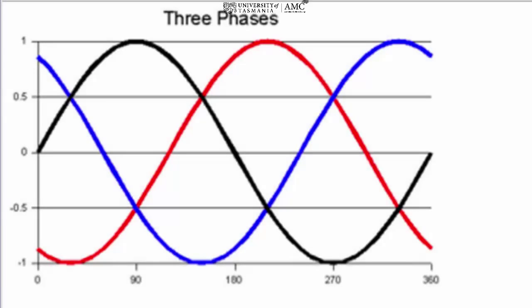The process of paralleling or synchronizing two generators or two alternators is essentially this: we have one generator which is on the board and it's producing our three-phase AC 415 volts, and you can see the three phases here as blue, black and red. Now if we want another generator to come on and operate powering the board at the same time, then we need to parallel or synchronize the alternators.